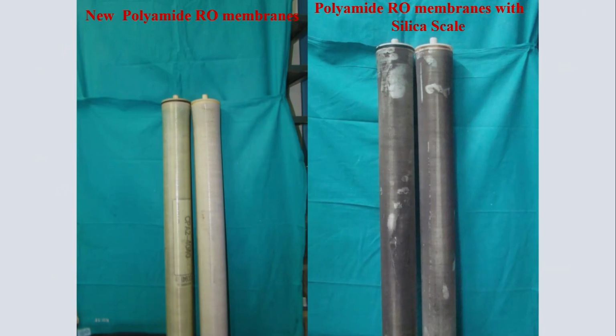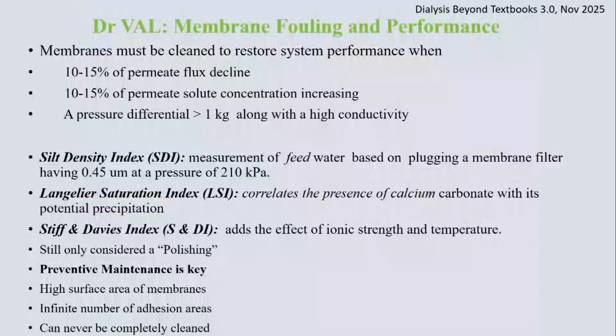So this is what membranes look like. Those are brand new polyamide Dow membranes, and this is a silica scale on a membrane which I had to replace after about 2 years, after which we introduced anti-scalant dosing pumps, because this was a component that was not checked, that silica is not usually checked when the water analysis is done. So you can take care of hardness with a softener, but if there is an amount of silica that's coming in the water, then you may need to add anti-scalant dosing pumps in such a situation. And it's automated. The pump's supply comes from the main control panel, so that as soon as the RO switches on, the anti-scalant also switches.